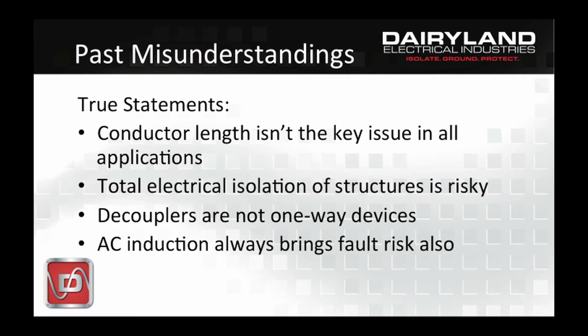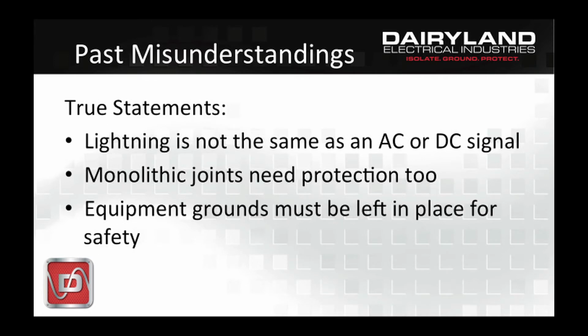Sometimes people think of decouplers as one-way devices, like a diode. Well, decouplers always are two-way devices. They will limit voltage in either polarity, and so there are some misunderstandings there that come up. Interesting topic. Finally, AC induction always has a fault risk. One can think of the steady state effects that they could experience on a pipeline, but then minimize or forget about fault conditions. And those are always present because the same induction that brings steady state conditions also can bring fault risks. And a couple of more.